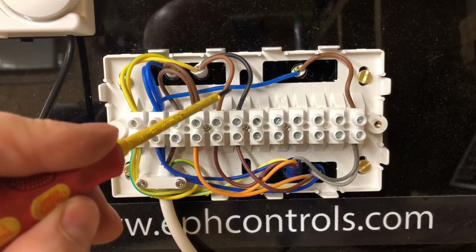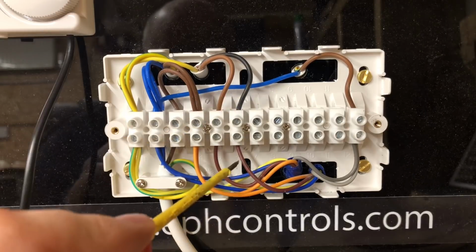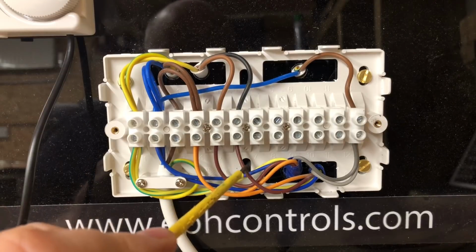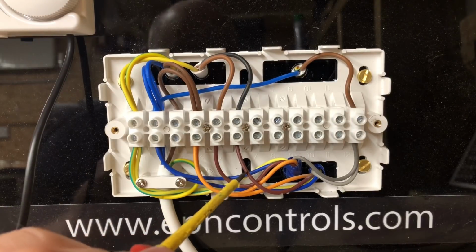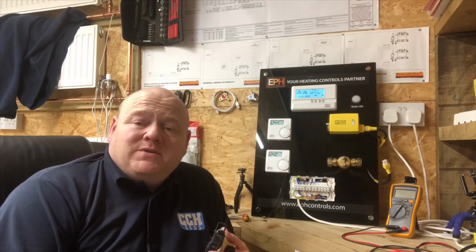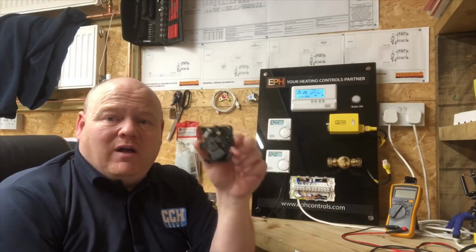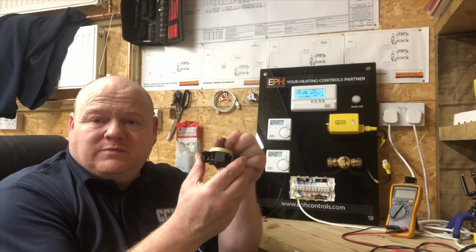So one of these is hot water and one of them is heating, but your switched wires go to your browns on your zone valve, and that would permanently open the zone valve as we've shown before. When the power then was turned off, so the demand was satisfied, then what happens is the spring in your zone valve actually moves this back.